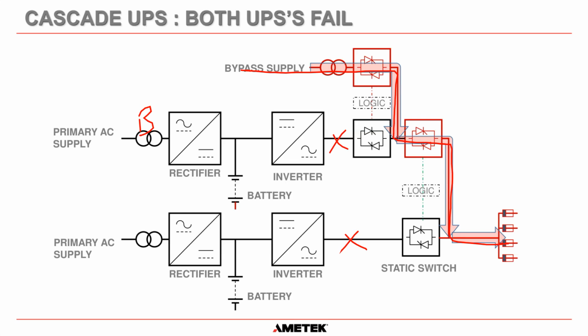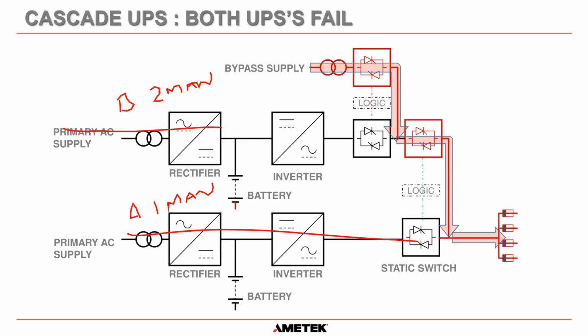Personally, I like Cascade UPS design. They're very flexible. There is no complicated logic between the two UPSs. And once again, for UPS A, it could be one manufacturer, and for UPS B, it could be a completely different manufacturer. There is no electronic communication between the two systems in a Cascade system. So you could have an AMETEK UPS as one, and you could have an old different type UPS in the other. It doesn't matter. Once again, it doesn't help when it comes to your spare parts. You would want to have two identical systems, so spare parts work in both systems, but in truth, you can have two different systems, which allows you a little bit of flexibility.